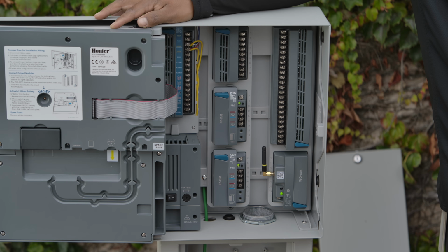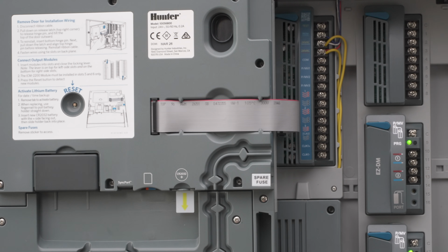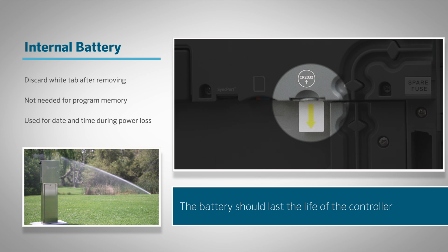A CR2032 battery is installed in the back of the facepack. The battery is not activated until you pull the white tab to allow the battery to connect. Simply discard the tab. This battery is not required for program memory. Its only purpose is to retain the current date and time in the event of AC power failure to the controller.